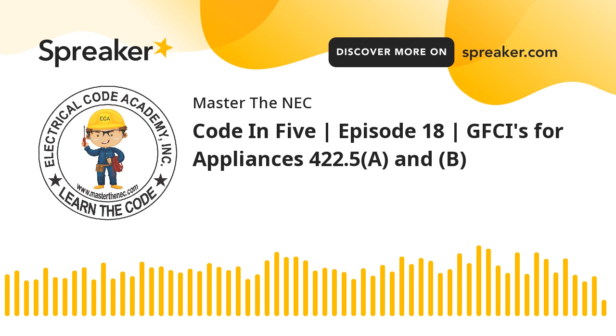So what are the seven appliances that require GFCI protection? Number 1, automotive vacuum machines. Number 2, drinking water coolers and bottle fill stations. Number 3, cord-and-plug-connected high pressure spray washing machines. Number 4, tire inflation machines. Number 5, vending machines. Number 6, sump pumps. And I'll remind you, this is not specific to commercial versus residential. This is across the board, so sump pumps do require, whether you like it or not, GFCI protection. And the last one, number 7, is dishwashers, which got relocated from 210.8(D). Dishwashers apply to both residential and non-residential applications.